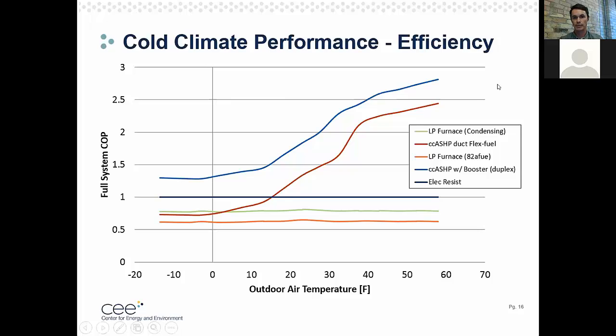So with the other heat pump system, we're looking at the dual fuel system, which is this maroon line. And as you can see, at these higher temperatures, it's still operating at around 200% efficiency down to between 30 and 40 degrees, but you see a steeper drop off in that efficiency. And that's because at a certain point, the heat pump can't meet the entire heating load of the home. And rather than that electric booster coming on to meet part of the load, with the dual fuel system, it's a hard switch. So you go from your heat pump operating and meeting 100% of that load to your furnace meeting 100% of that load.